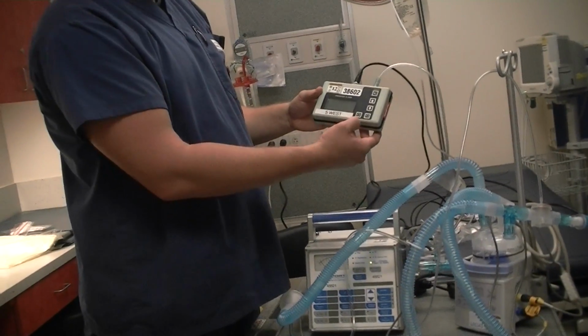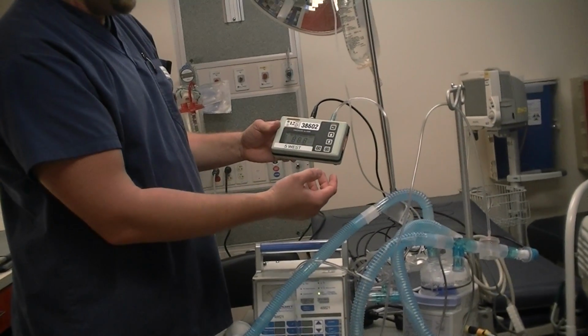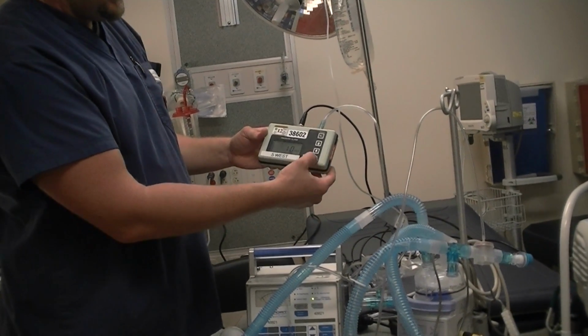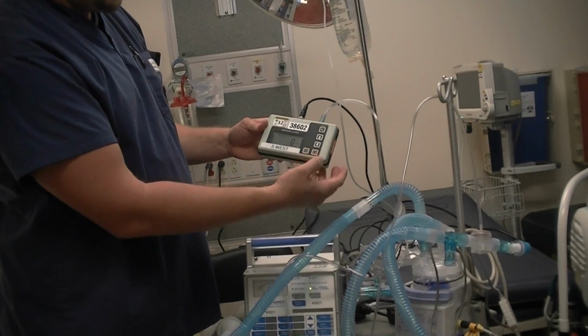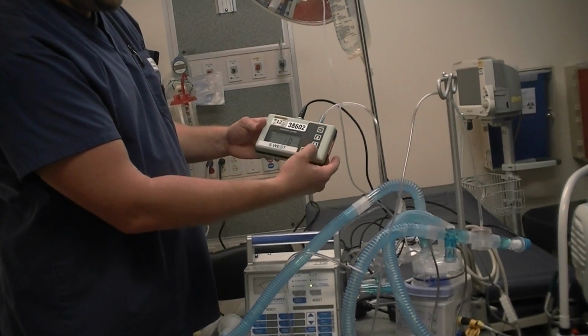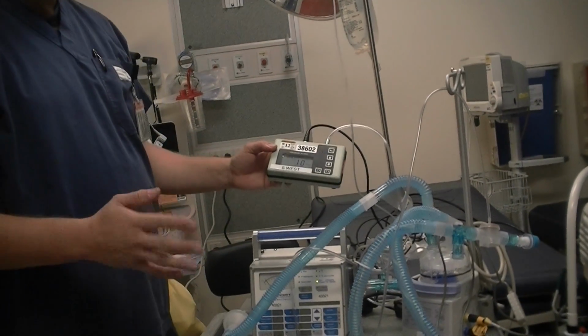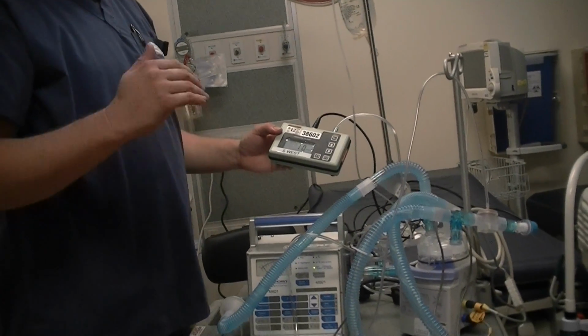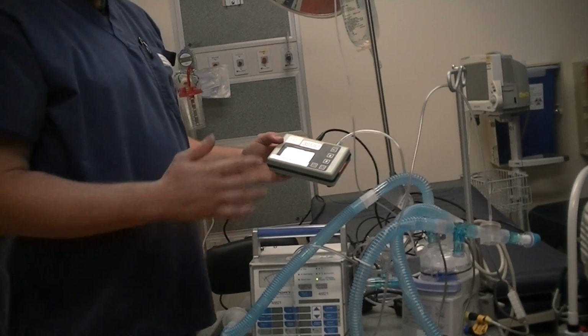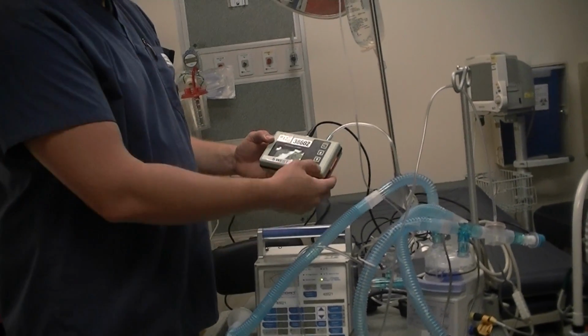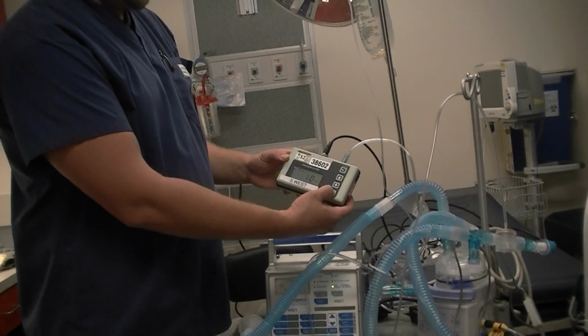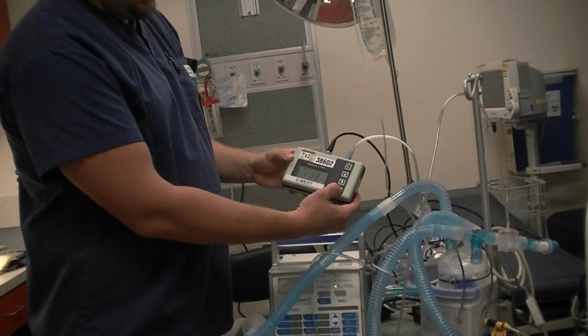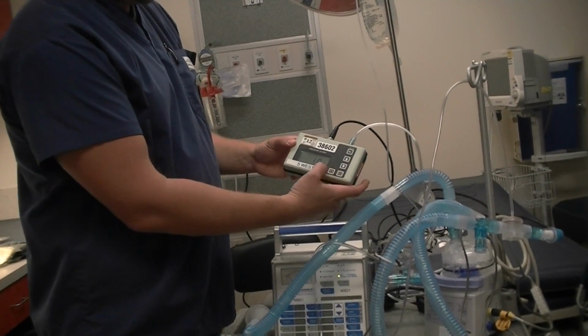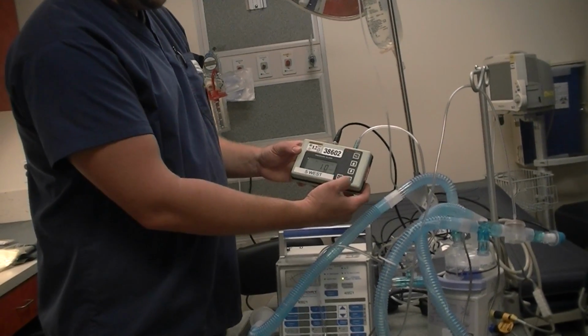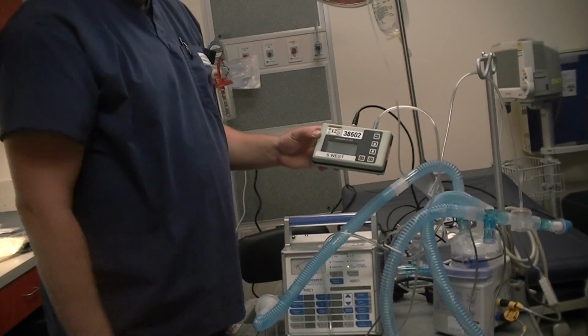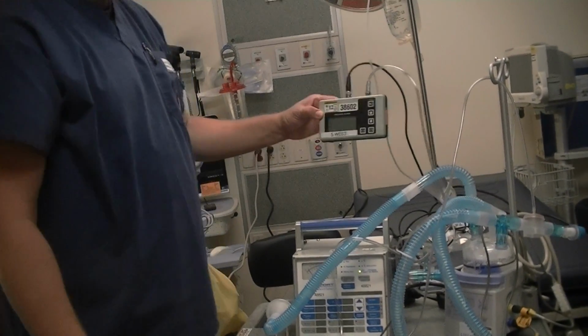Okay, to adjust your pressure line, you're just going to press the on button. To make changes, you press enter. Enter again. You may go up and down on your settings. You want it about 5 to 7 centimeters of water pressure below your PIP. So if you have a PIP of 20, you might want to set this about 15 with a delay of maybe 5 to 6 seconds. Okay? To get out of the setup, keep pressing enter. To turn it off, press enter and the on-off button, and we're all done with that.